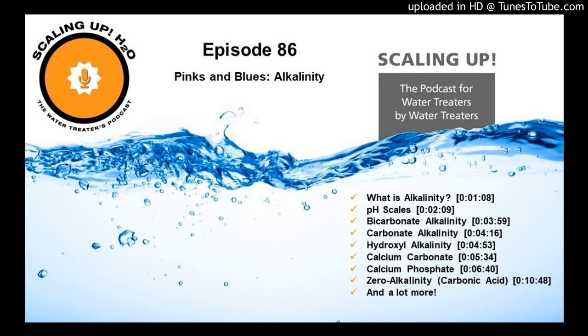Now from the range 4.3 to 8.3 pH, that is where bicarbonate alkalinity exists. You might also hear that called M alkalinity. All right, so hopefully everybody has that visual. Now we're going to go to 8.3. From 8.3 to around 10.3, these numbers are all ish, as most water treatment numbers are, that's where carbonate alkalinity exists. We might hear that called P alkalinity.